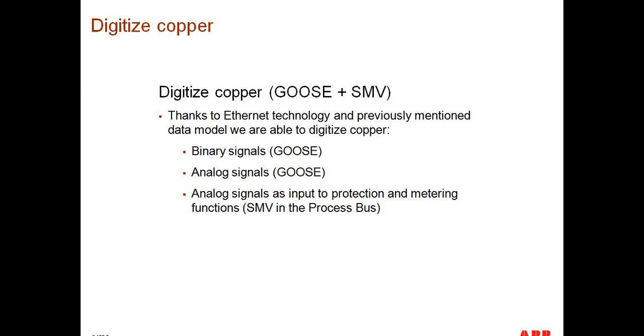The idea of the process bus is that, instead of having to hardwire current transformers and voltage transformers onto the back of the relays, the information from current transformers and voltage transformers is digitized by a device known as the merging unit, and the merging unit publishes the analog information on the network. Then any device that's connected to the network can subscribe to this. So it not only provides the cost savings of reduced copper, but since there's really no additional cost to subscribe to additional analog streams, you can have schemes where you take in more analog information from more devices to perform better protection schemes.